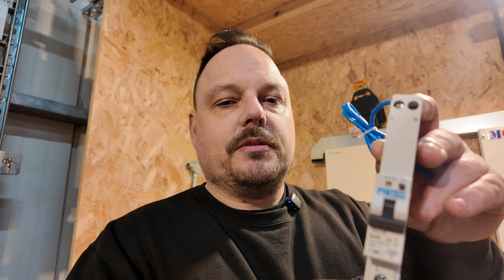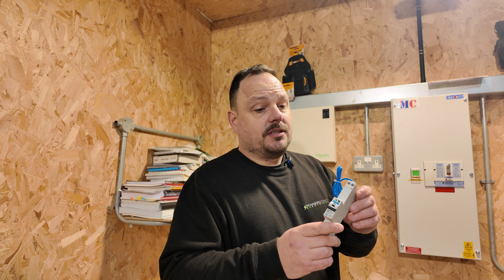This is a single module RCBO. So bring this in a little bit closer. Have a little look at that if it will focus. I think it's focusing on my head. So I'll put it right next to me. But basically this is also a type B. So this is a type B single module RCBO, and this one's rated as a B40. It's 30 milliamp and it's 10 kA. So this is fixed in its values and settings and the way it operates. But it does have the product standard, or the British standard, of 61009-1, which is what we need for our RCBOs in terms of the wiring regulations.